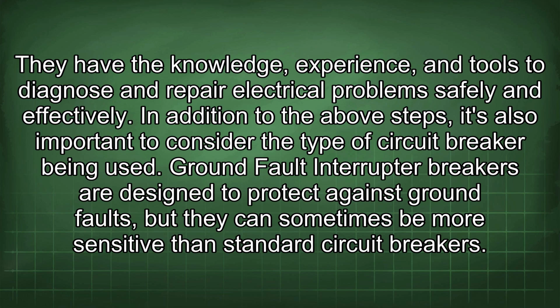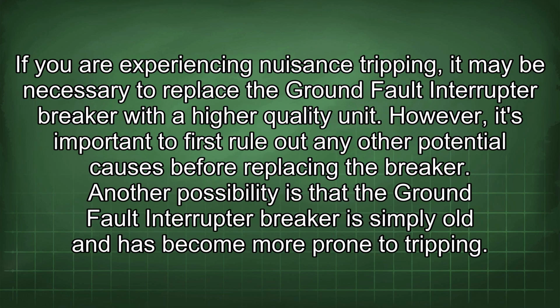In addition to the above steps, it's also important to consider the type of circuit breaker being used. Ground fault interrupter breakers are designed to protect against ground faults, but they can sometimes be more sensitive than standard circuit breakers. If you are experiencing nuisance tripping, it may be necessary to replace the ground fault interrupter breaker with a higher quality unit. However, it's important to first rule out any other potential causes before replacing the breaker.